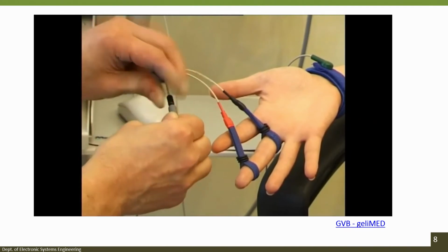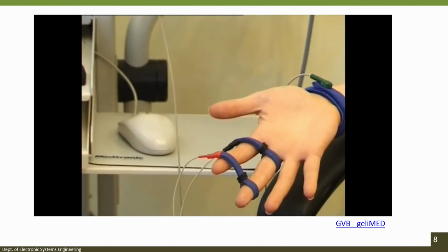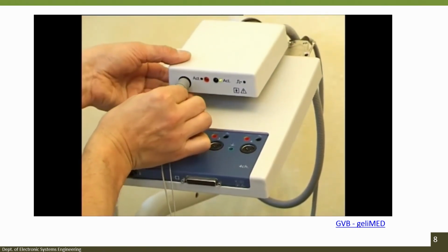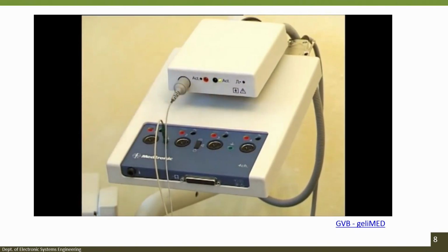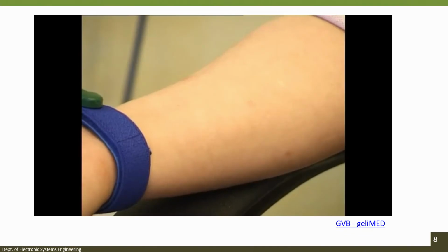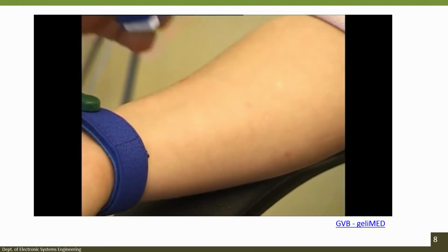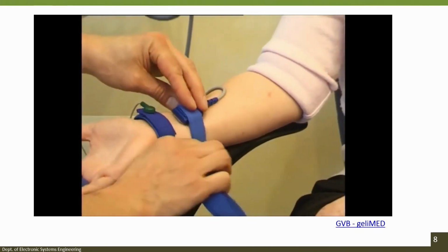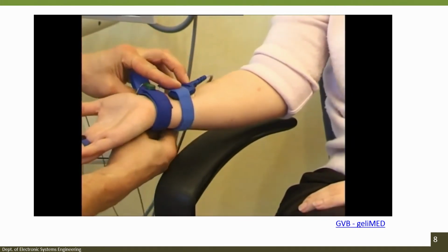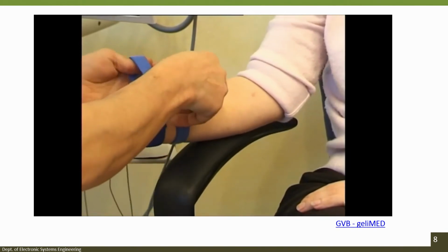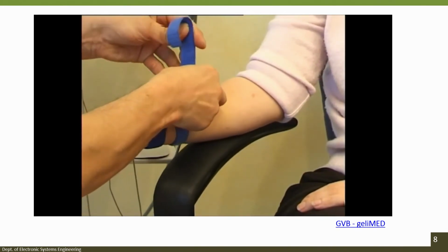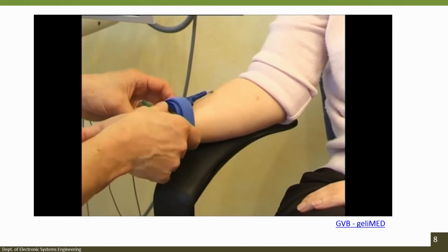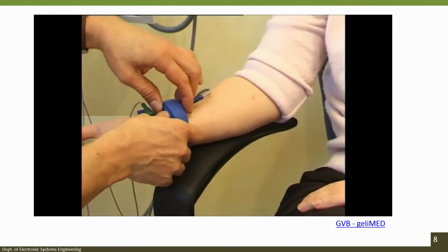Finger-toe stimulation electrodes are also a part of the multifunctional system and can now be connected to the EMG instrument by the multifunctional cable. The sensitive recording electrode is positioned directly over the nerve above the wrist, attached using Velcro tape, and then connected to the EMG instrument. This stimulation and recording electrode has already been used as a stimulation electrode in the previous section.